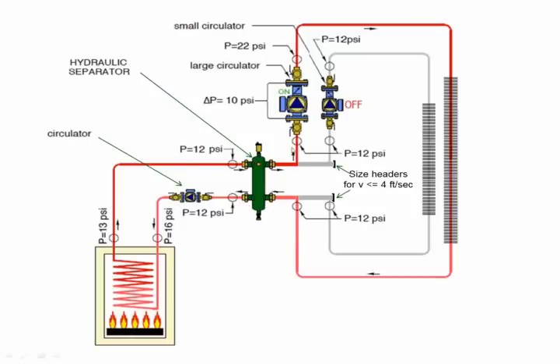By doing so, we have decoupled this pump. And now we can see what the effects are on the pressure. Okay, so we start with our expansion tank. Now, with the hydraulic separator, we can put our expansion tank basically anywhere around the hydraulic separator because there's no pressure drop around the hydraulic separator. Okay, so let's say we put it here. So 12 psi is the starting point, right? Which means basically this is 12 psi. We raise our pressure 10 psi, come back around from 22 coming off the pump, back around to 12, okay?